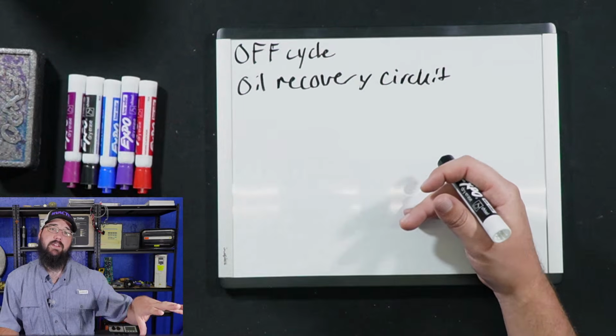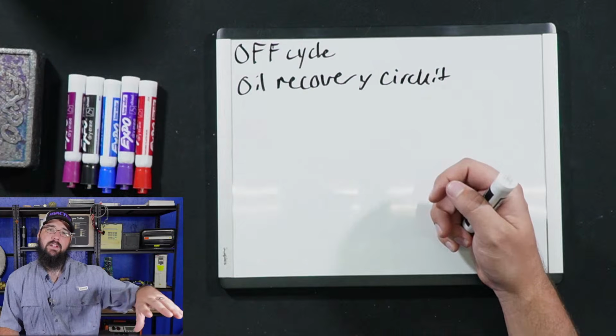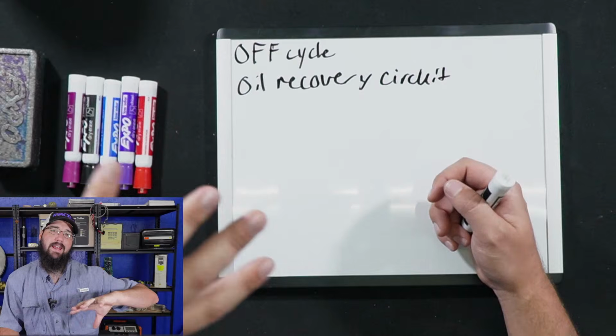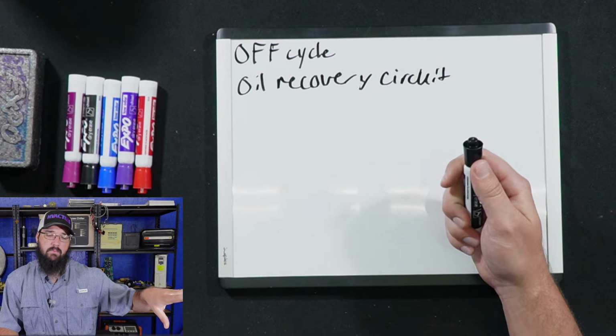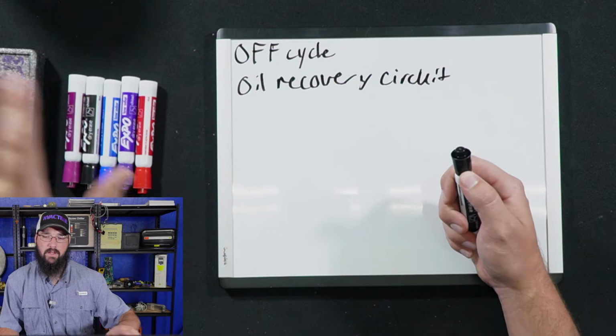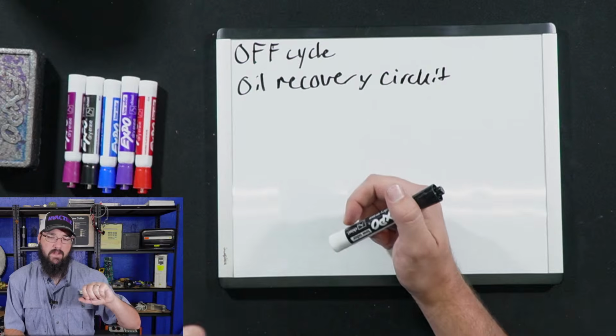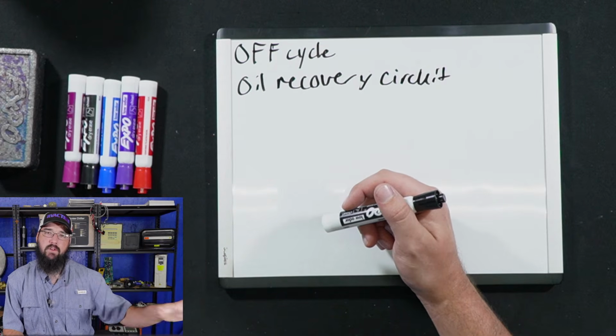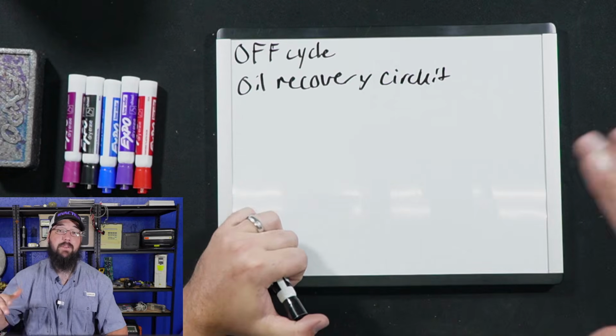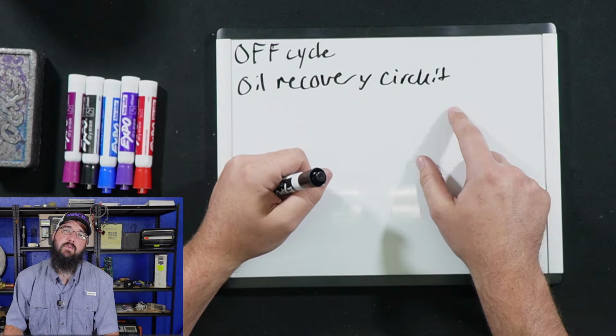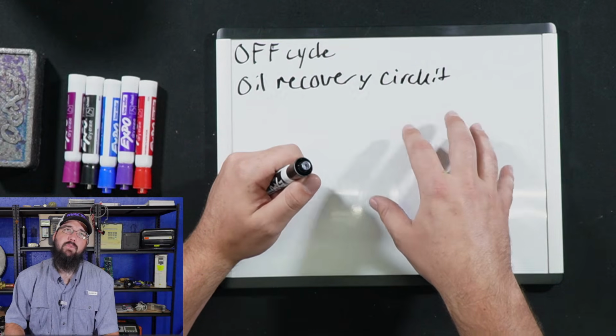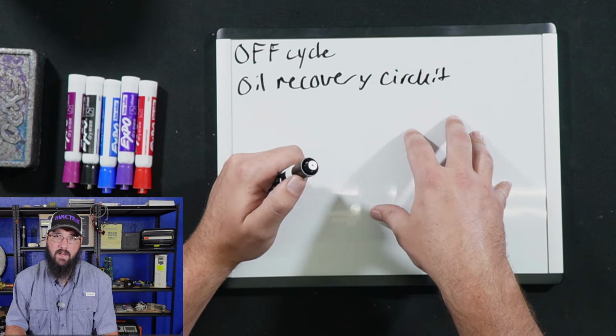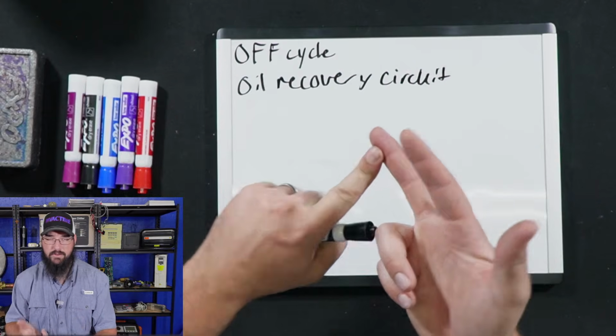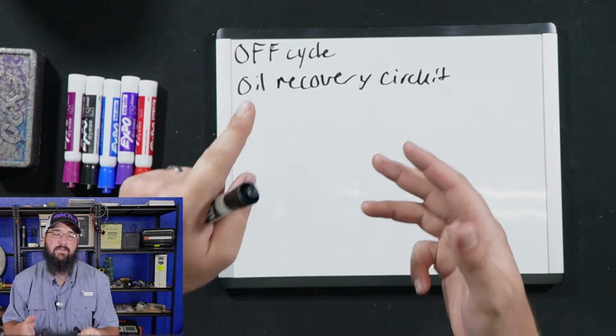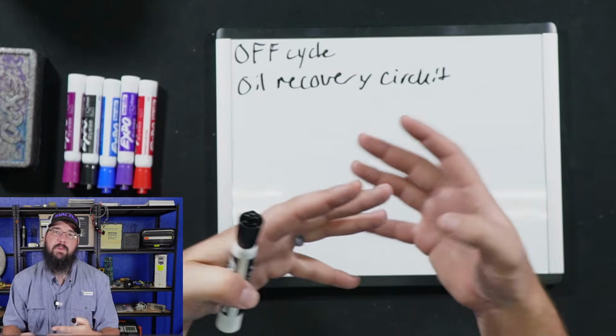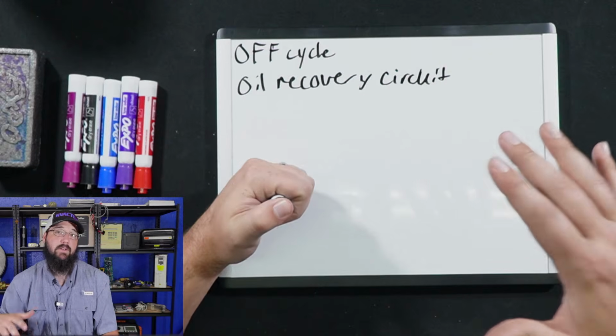And this is going to be leaving the eductor. So if we leave the eductor block or the gas pump, whatever the case may be, and head to what we're feeding back into, whether it be the compressor, the oil sump, whatever the case, if that's not feeding correctly, or if the filter's not allowing enough flow through it, that can allow the oil to begin to stack up in the evaporator. So that's one example. Another would be if the refrigerant level starts to run too low or too high in the evaporator, which could be undercharge, overcharge, liquid level sensor issues, metering valve issues. Those would be reasons we may have improper liquid levels in the evaporator.